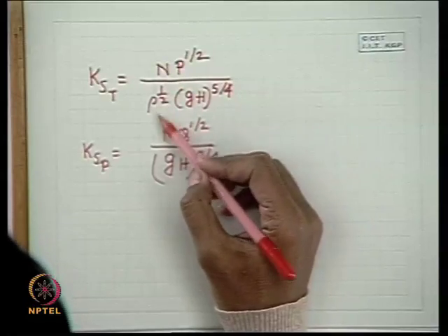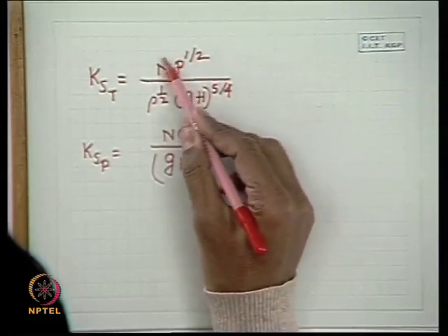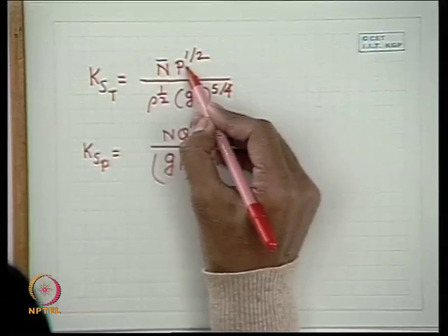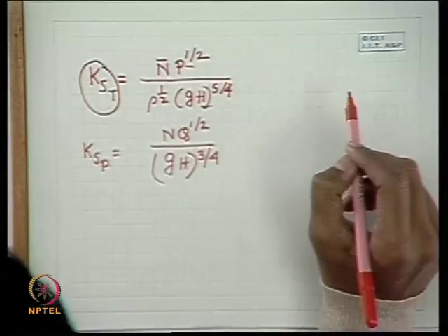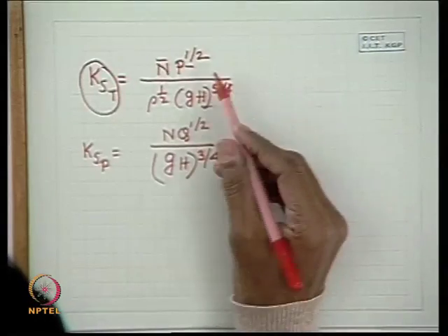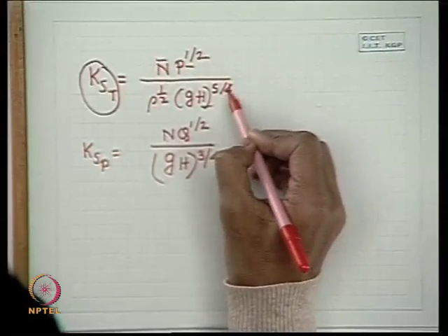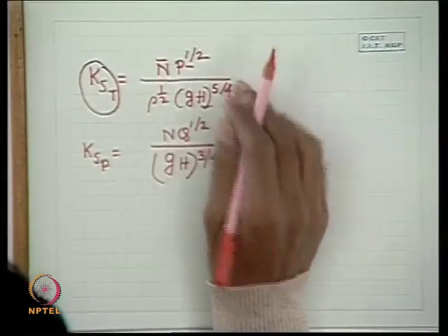That is not desirable, to run the machine at those operating conditions. Therefore, you see here again that for a particular machine of a particular design, there is a unique set of values of N, P and H which give a unique value of KST for its running at maximum efficiency.